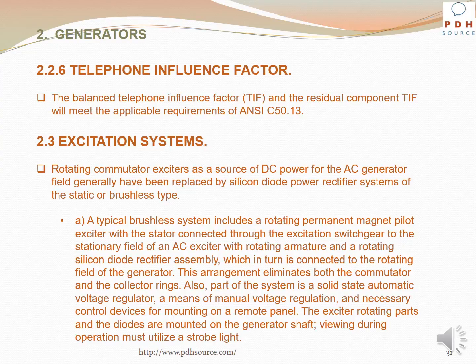Rotating commutator exciters as a source of DC power for the AC generator field generally have been replaced by silicon diode power rectifier systems of the static or brushless type. A typical brushless system includes a rotating permanent magnet pilot exciter with the stator connected through the excitation switchgear to the stationary field of an AC exciter with rotating armature and rotating silicon diode rectifier assembly, which in turn is connected to the rotating field of the generator. This arrangement eliminates both the commutator and the collector rings.